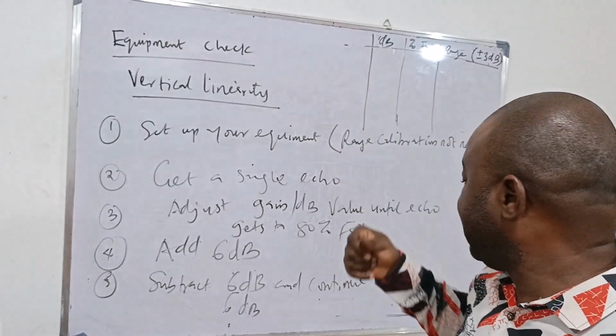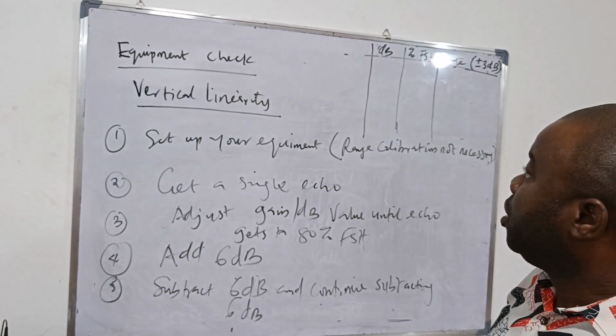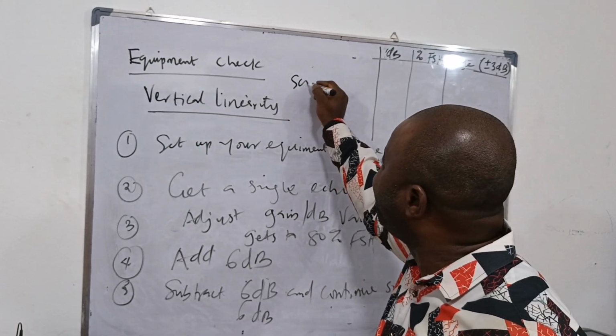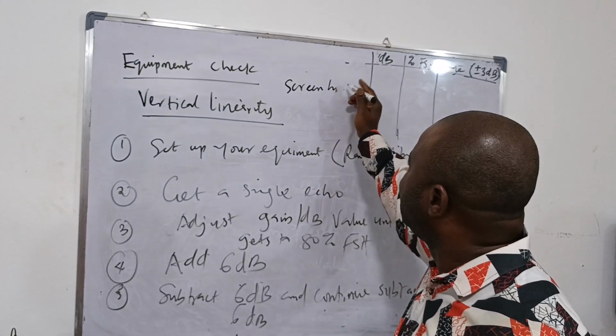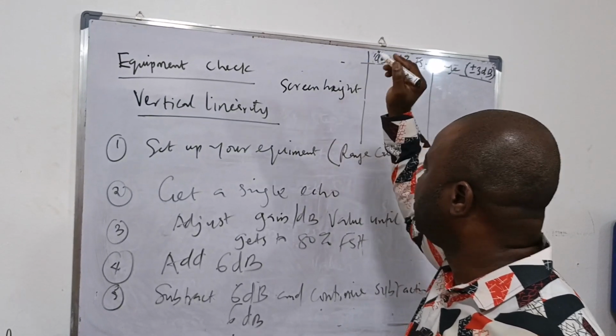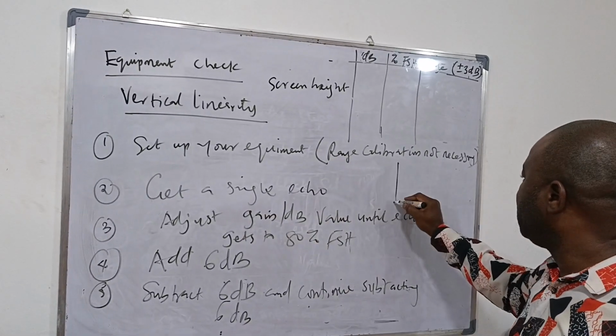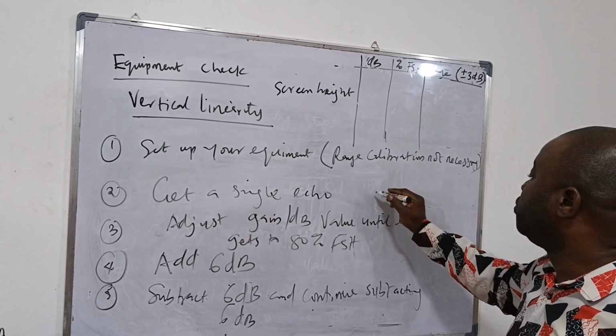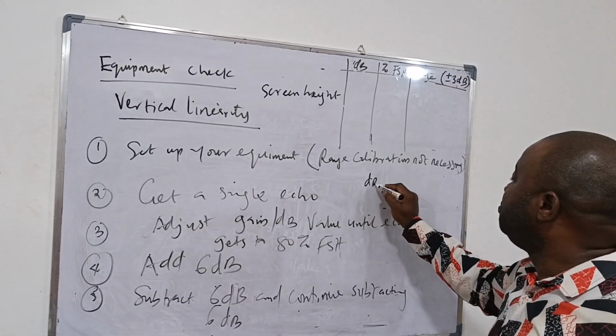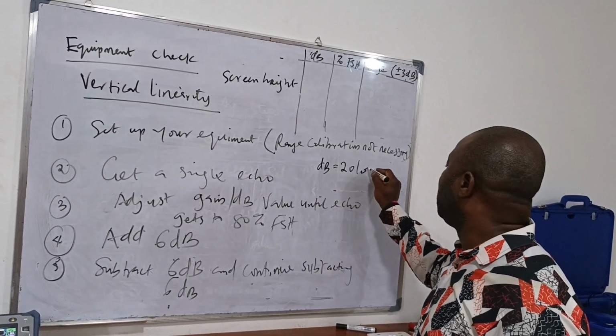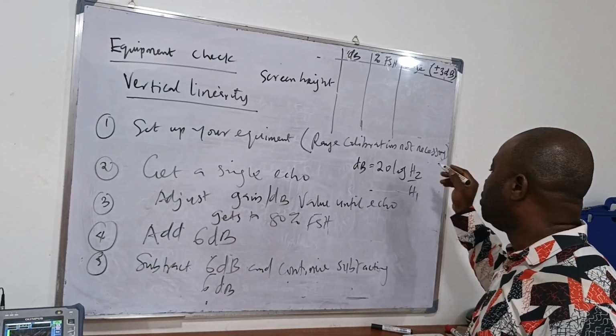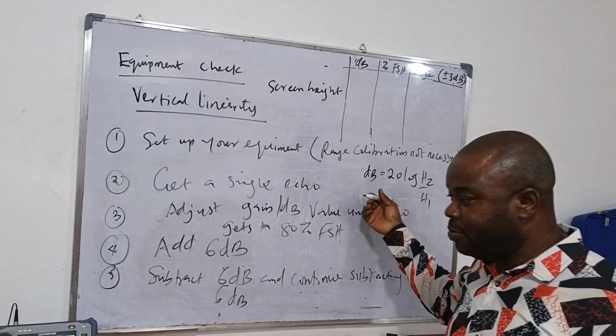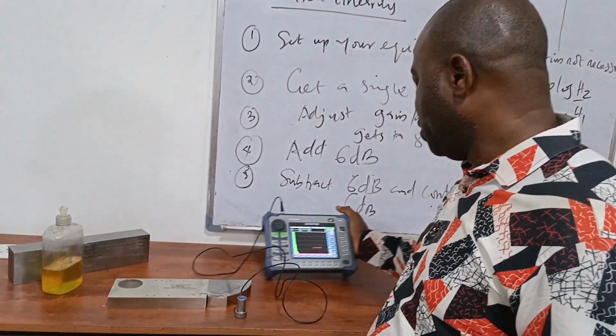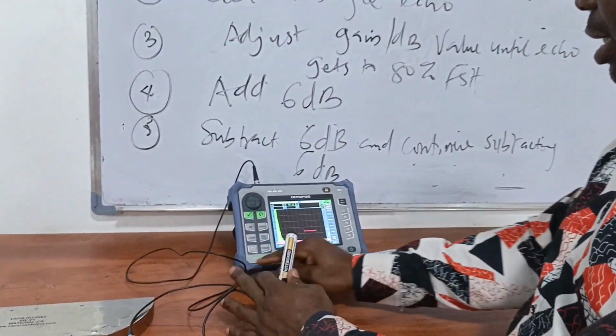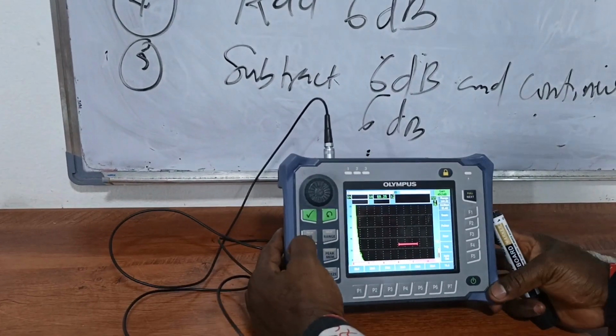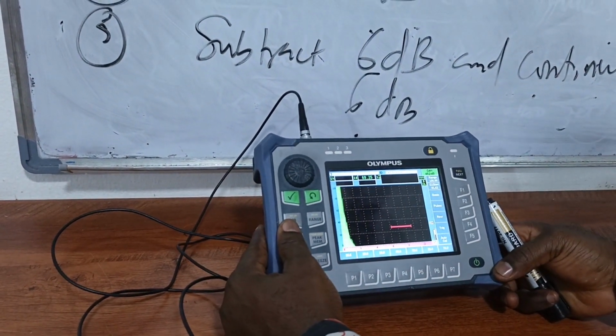Now, if we look at the vertical linearity, another name for vertical linearity is screen height linearity. Earlier on, I told you linearity follows your dB rule, which is dB is 20 log h2 over h1. Just to give a perspective to this dB thing, if you look at your machine, you will always see a button. As in this case, you will see it as dB. In some other machines, you will see it as gain.